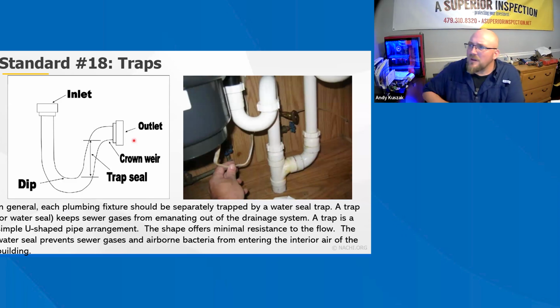Traps. So in general, each plumbing fixture should be separately trapped by a water seal trap. A trap or water seal keeps sewer gases from emanating out of the drainage system. A trap is the simple U-shaped pipe arrangement. The shape offers minimal resistance to the flow. The water seal prevents sewer gases and airborne bacteria from entering the interior air of the building. Traps shall have a water seal of at least 2 inches and at most 4 inches in depth. Traps for floor drains should be fitted with a trap primer or should be of the deep seal design.